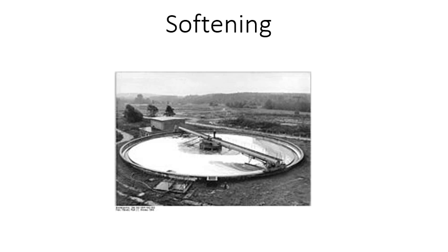Reducing pH too fast by adding too much CO2 can cause some hardness to become soluble again and make bicarbonate hardness again, like you didn't treat for the hardness at all. Lime soda softening is chemically intensive.